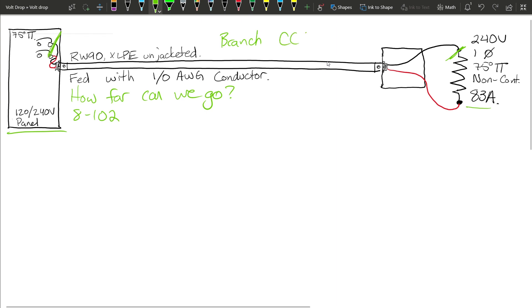So from that final overcurrent device all the way to the load, we are allowed a 3% volt drop. Essentially, 3% of 240 volts is the maximum voltage we can drop before it starts to cause problems at the load. Now that we've determined we're working with a 3% volt drop, let's take a look at Table D3.